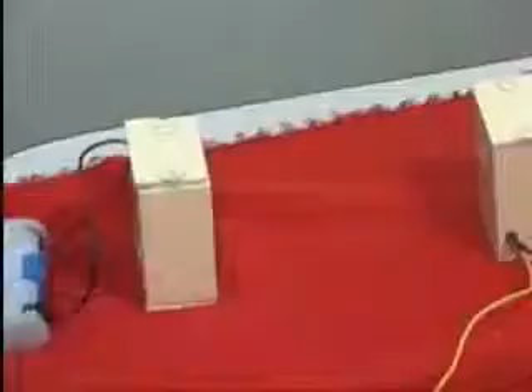Now I will test with the encoder. On the transmitter part, when the battery is connected properly and the receiver and transmitter are both in line, if the installation is proper, then on the yellow line you will always find it high. If you look at this multimeter and these two points, the yellow line is high. This 5 volts on the yellow line indicates the beam is present.